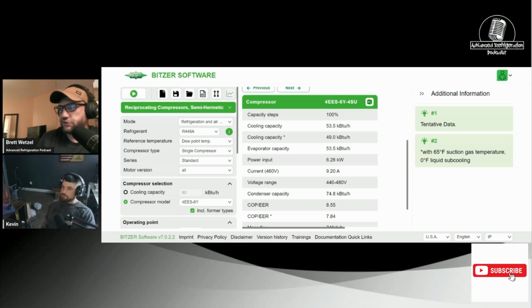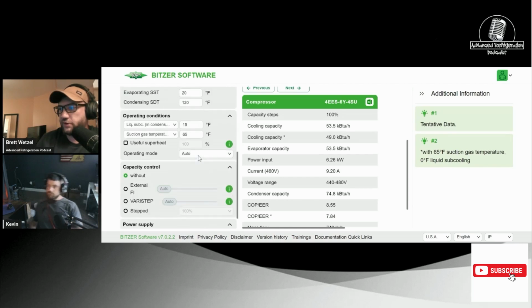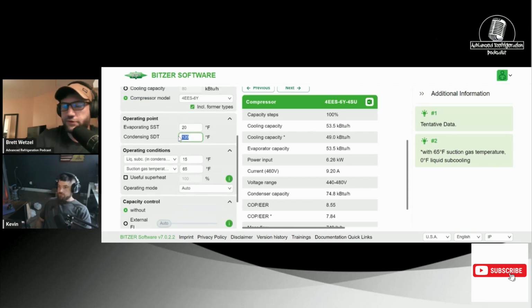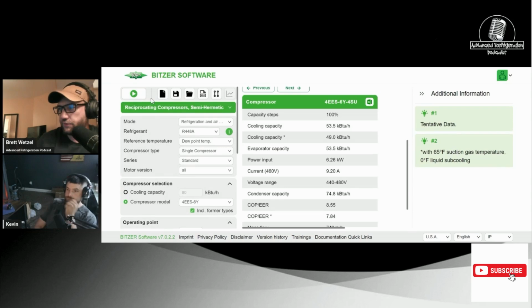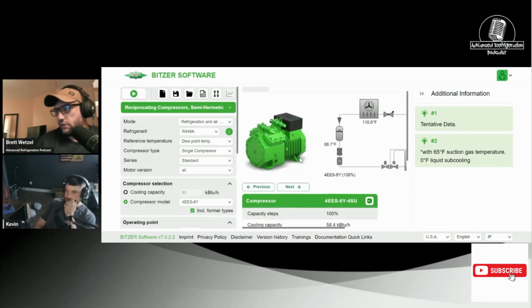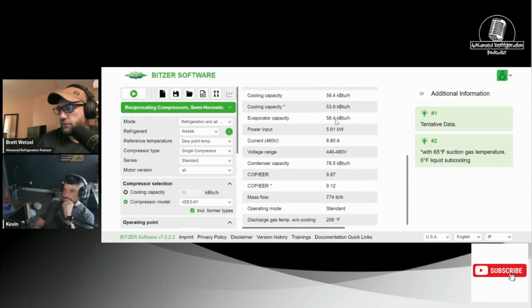Right, so here I'm going to just take a screenshot so I can snap and compare. And then I'm just going to run it one more time back to the way we had it at 110 degrees. Play. And here we go. So cooling capacity 53.9 kBTU. And when it was higher, 53.5. So yes, the capacity did in fact go down when we raised that head pressure up.